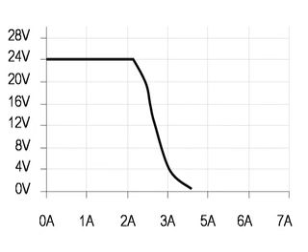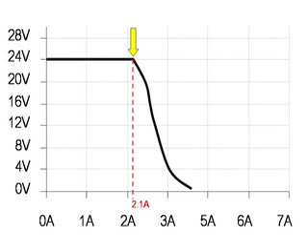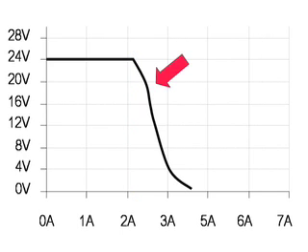This is the graph of our 2.1 amp fold forward design power supply. You can see that at no current the output is 24 volts DC and remains steady until the current reaches 2.1 amps. Any current after 2.1 amps causes the power supply to go into overload, which also causes the output voltage to drop, but the overall output wattage is maintained.